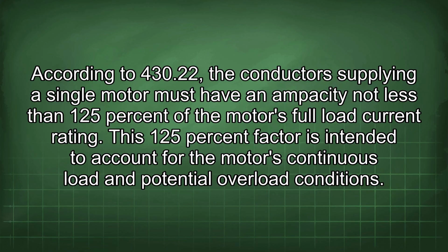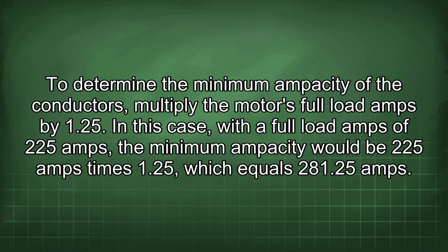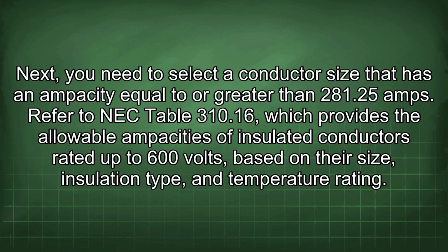According to 430.22, the conductors supplying a single motor must have an ampacity not less than 125% of the motor's full load current rating. This 125% factor is intended to account for the motor's continuous load and potential overload conditions. To determine the minimum ampacity of the conductors, multiply the motor's full load amps by 1.25. In this case, with a full load amps of 225 amps, the minimum ampacity would be 225 amps times 1.25, which equals 281.25 amps.